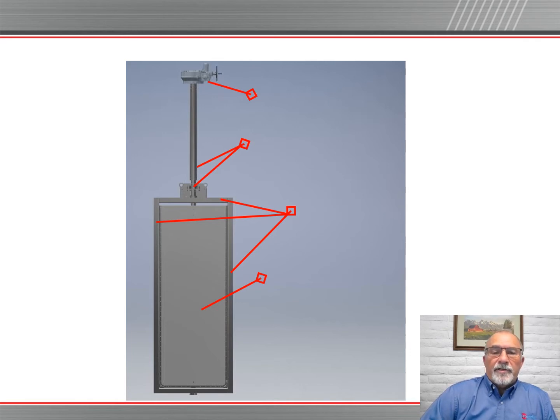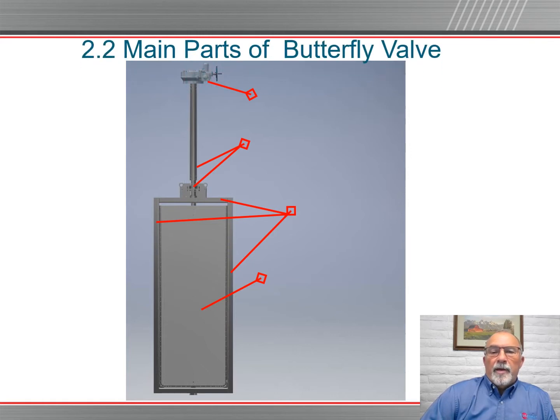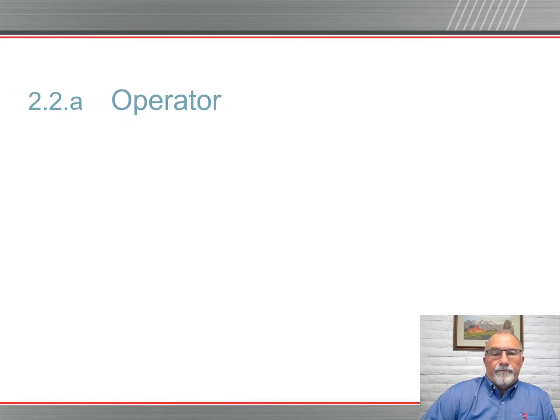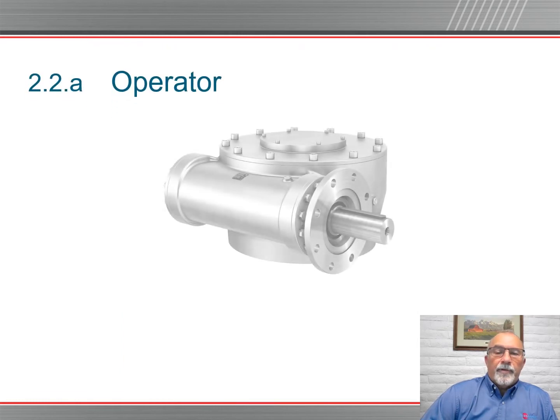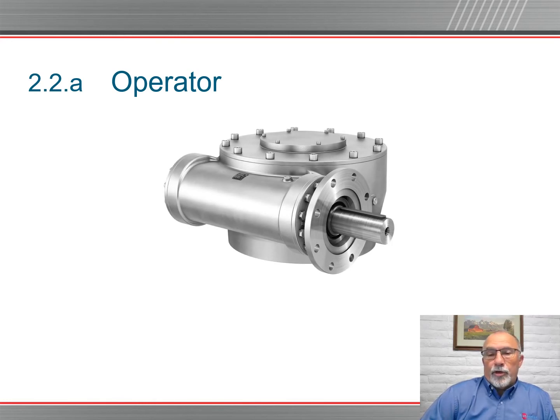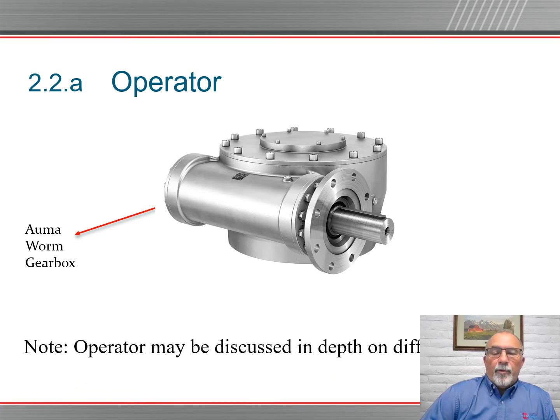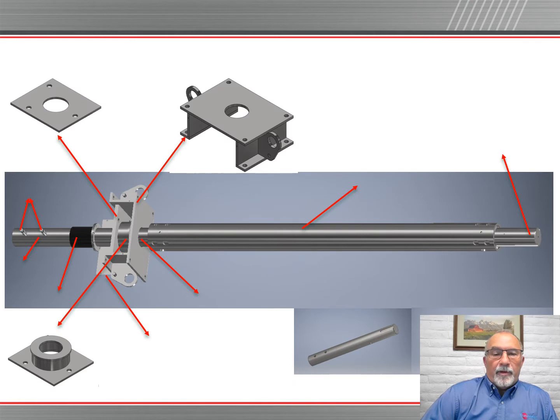On this project, they're very similar in design to this in that they're very narrow and very tall. The main parts of the butterfly valve include an operator, the torque tube and bonnet or the extension, the frame structure, and the cover. The operator is a large gear-driven quarter-turn actuator or operator. In your case, it's an Auma Worm Gearbox. The operator may be discussed in depth on a different topic.